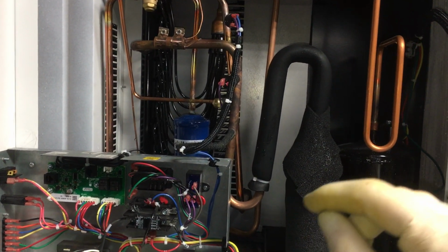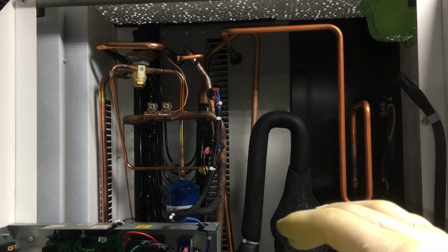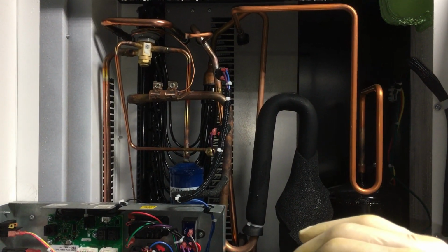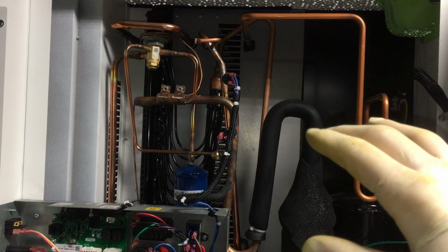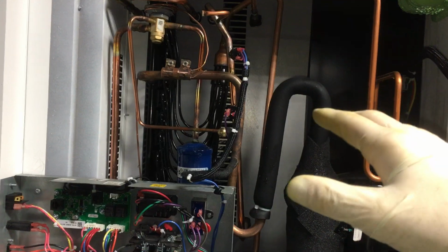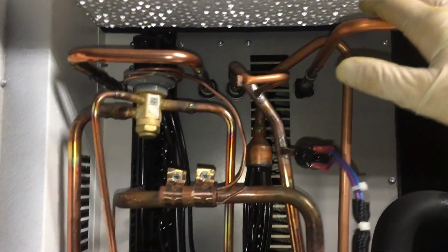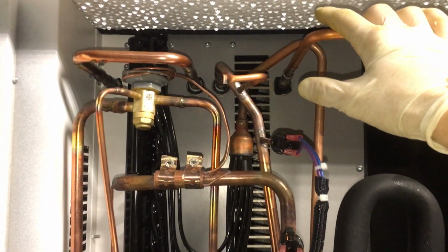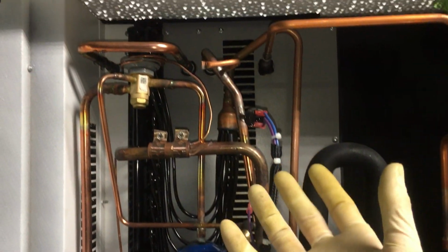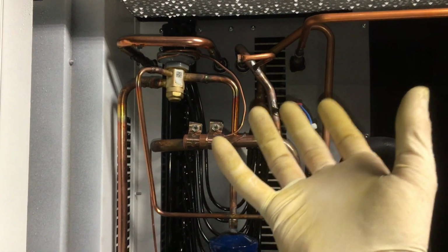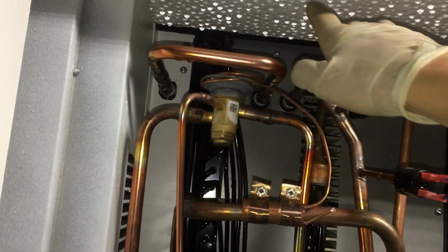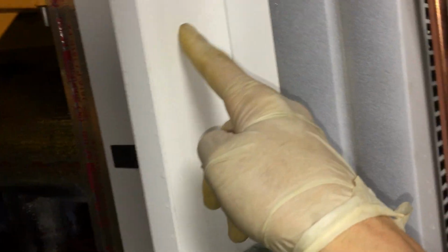Well, in this locality, it just got down to 32 degrees outside, and even within the warehouse it got down into like 39-40 degrees. So the area that it's dehumidifying is roughly 70-80% humidity at 81 degrees Fahrenheit. So you have this saturated, moisture-laden air with tons of water in it, and as the air passes and comes into here, it contacts the outer surfaces. All over here is wet. All these outer surfaces, this plate, all this water here, this is all condensation.